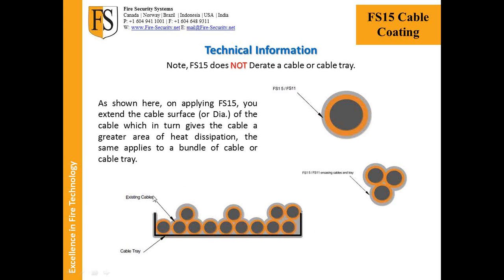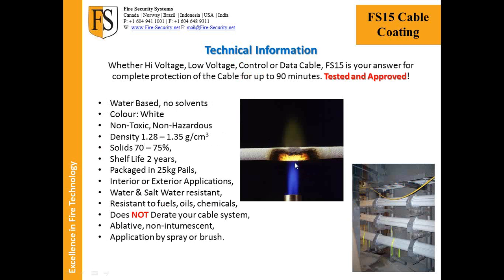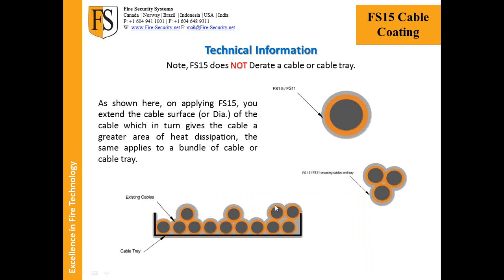Because you are effectively wrapping a blanket, encasing the external surface of that cable tray in coating, no flame can get into that cable tray, and in reverse, no flame can get out of that cable tray. So there is zero oxygen in this area once you have encased that cable tray. Okay. So there is no possible way that a fire can get out or a fire can get in. Because if we flip back to here, you'll see what the cable coating does under fire. Now this is a gas burner, so it's running at around 1600 degrees Celsius. There's zero flame spread. It will eventually burn away either side, and eventually after 90 minutes get through to your cable and lose your integrity. But what it's not doing is spreading the flame. And that same thing will apply to the base of your tray, to the top of your cable.